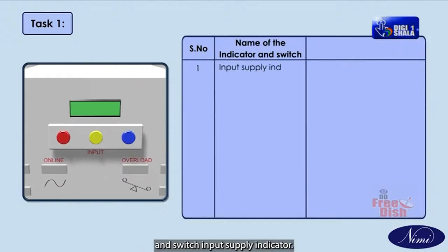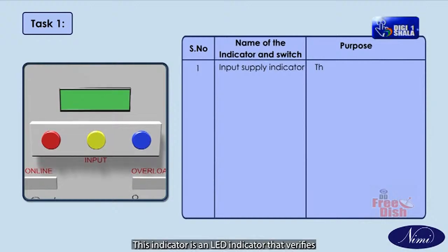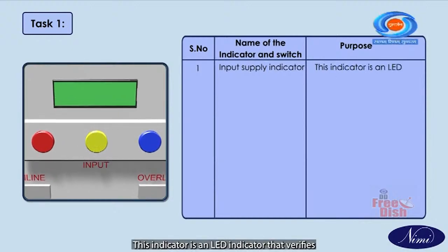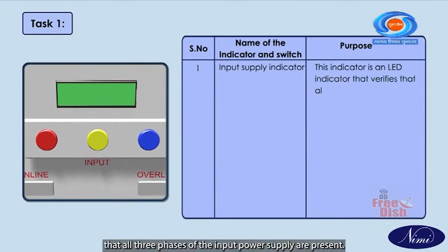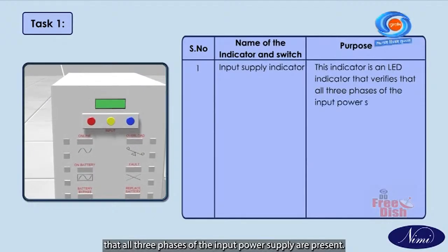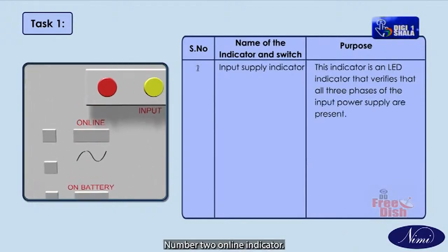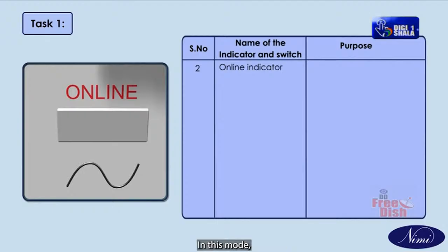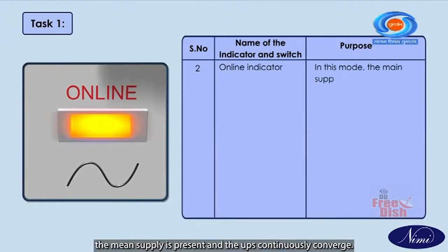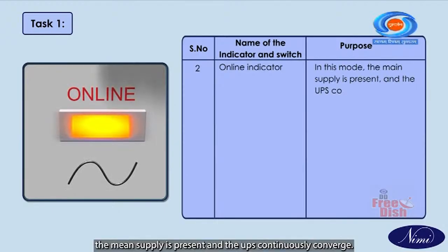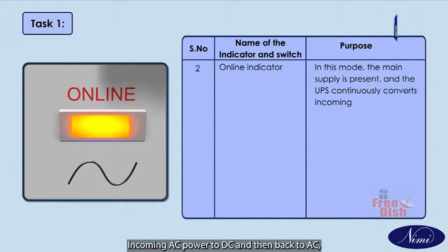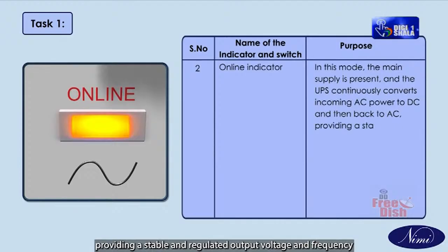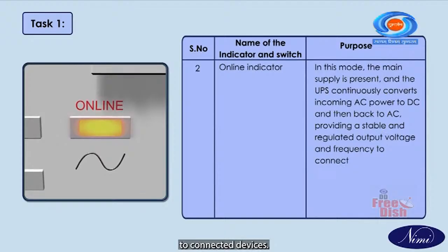Input supply indicator. Purpose: this indicator is an LED indicator that verifies that all three phases of the input power supply are present. Number 2. Online indicator. In this mode, the main supply is present and the UPS continuously converts incoming AC power to DC and then back to AC, providing a stable and regulated output voltage and frequency to connected devices.